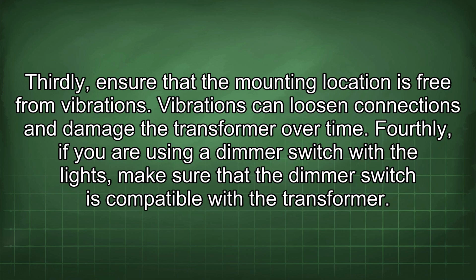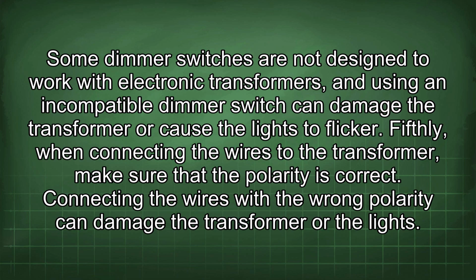Thirdly, ensure that the mounting location is free from vibrations. Vibrations can loosen connections and damage the transformer over time. Fourthly, if you are using a dimmer switch with the lights, make sure that the dimmer switch is compatible with the transformer. Some dimmer switches are not designed to work with electronic transformers, and using an incompatible dimmer switch can damage the transformer or cause the lights to flicker.